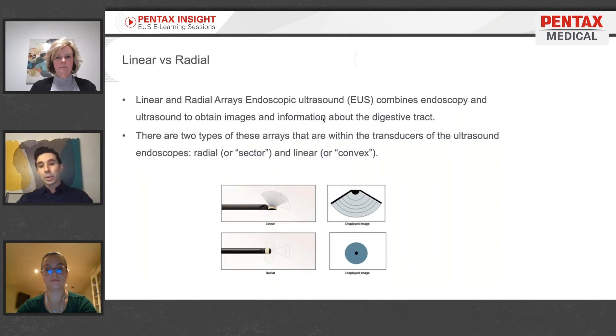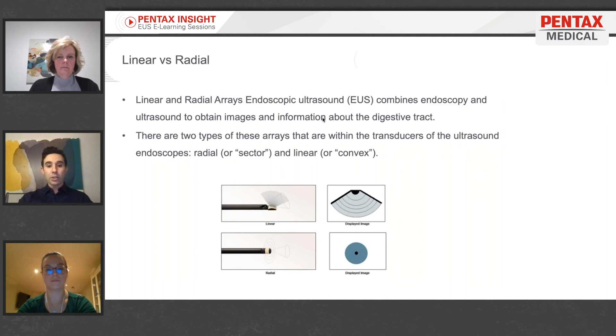The two types of endoscopic ultrasound scopes are linear and radial — those are the terms we use to describe our two scopes, and they relate to how they image. The radial scope in most instances is a forward-viewing endoscope, so endoscopically it looks exactly like a gastroscope — when you're driving forward, you can see exactly where you're going. The radial scope images in a 360-degree form around the axis of the endoscope.